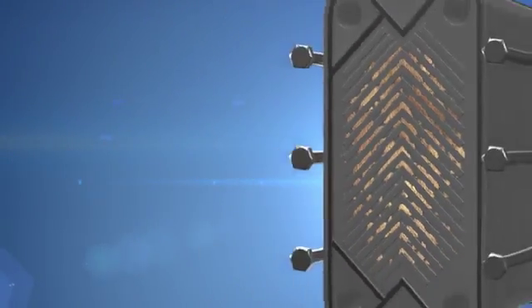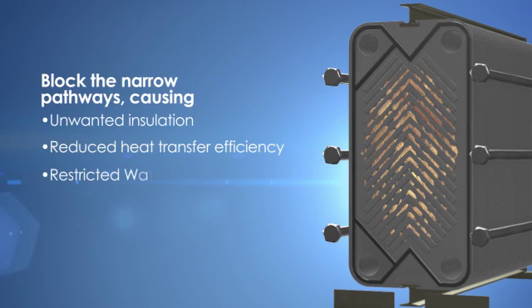Over time, accumulated scale, along with biofilm that consists of bacteria and algae from the process liquid, block the narrow pathways, causing unwanted insulation, reduced heat transfer efficiency, restricted water flow, and higher energy consumption.